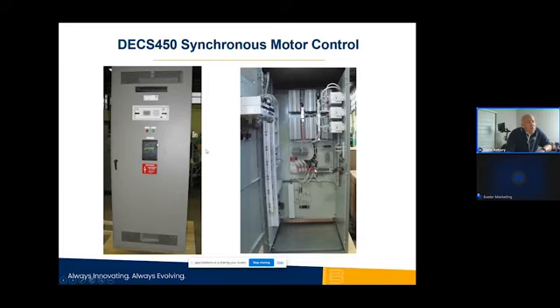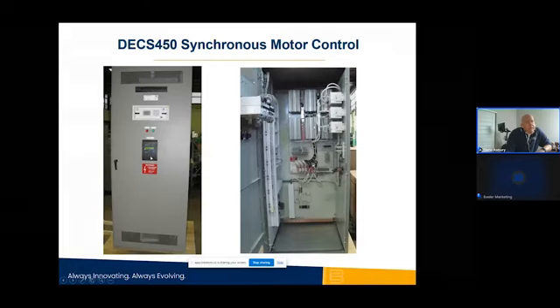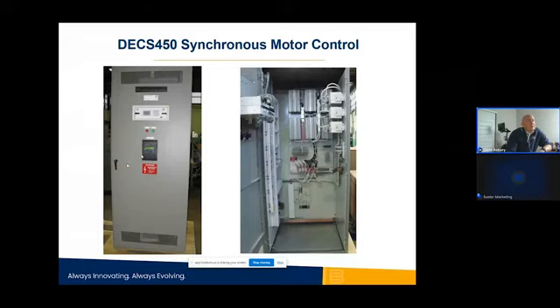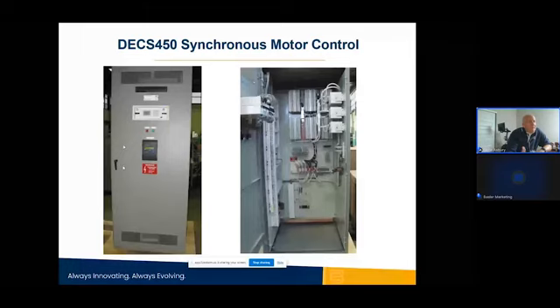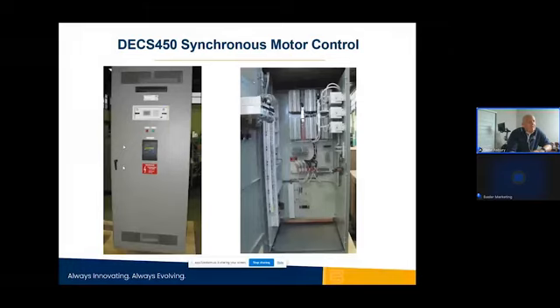You've got a field application relay here, and I don't see a discharge resistor or a starting resistor. So they probably reuse the existing starting resistor, because that's a very crucial part of that motor. It's a specially designed resistor just for that motor. If a customer wants us to replace that starting resistor, we have to give the exact measurements of that resistor so we don't affect how the motor starts. You want to provide enough synchronizing torque during the starting process, but you don't want to overheat it. So it's a very, very crucial part.